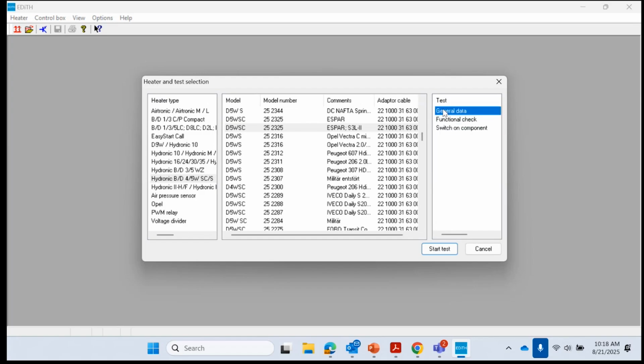The general data will give us an overview of the operating hours and the fault codes that are stored in the ECU. The switch on component test will allow you to test components individually, like the fuel pump, the glow pin, the fan motor, and the coolant pump. All of them can be switched on and off independently to test. So it's a very good way of isolating whether the component is at fault or not. And then the functional check is like an overview of the heater operation. It's a full comprehensive check.